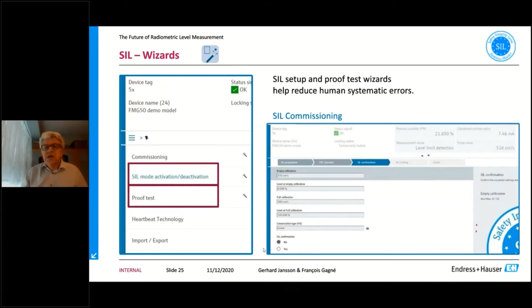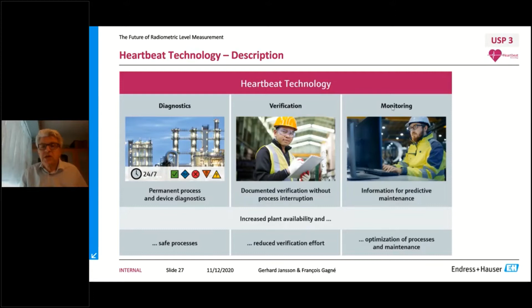Heartbeat is something a little bit the same thing to improve the safety, but we'll talk about that here. So heartbeat for Endress+Hauser is something that you find with many of our instruments today, and it's in 3 parts: diagnostic, verification, monitoring. If we look at the diagnostics, this is something that is going on 24/7. It's going through the instrument, checking its own health, and going through a number of diagnostics, in this case 54 of them, very much checking the health of the instrument.